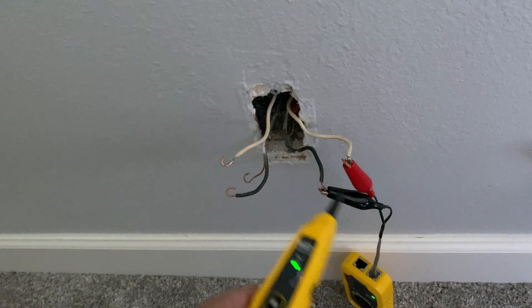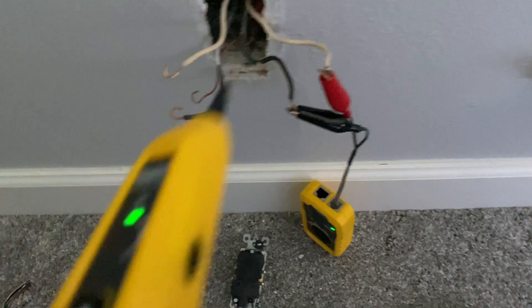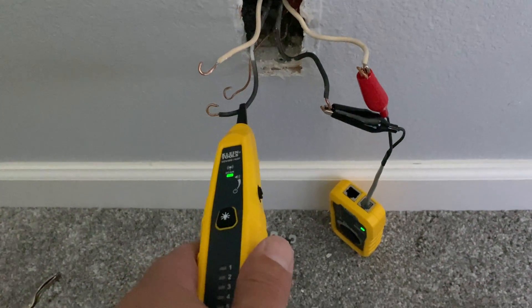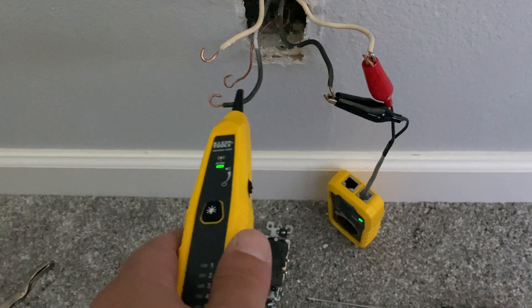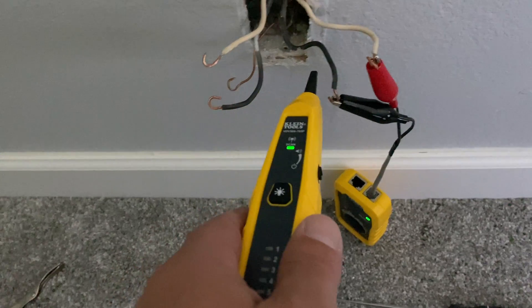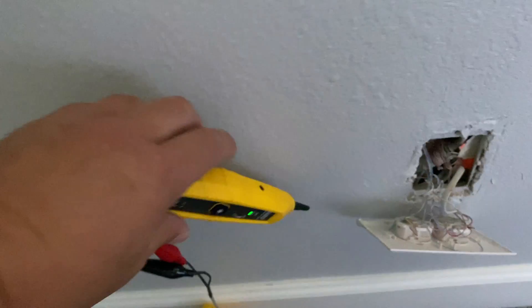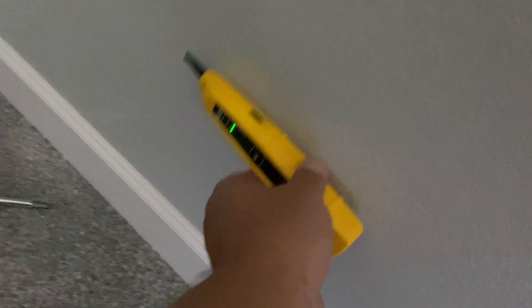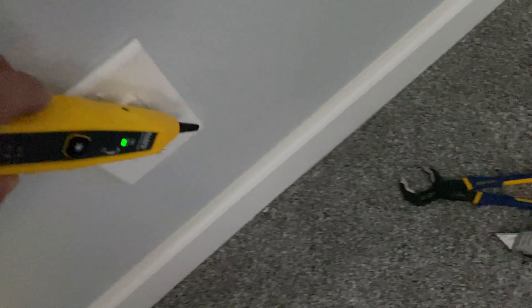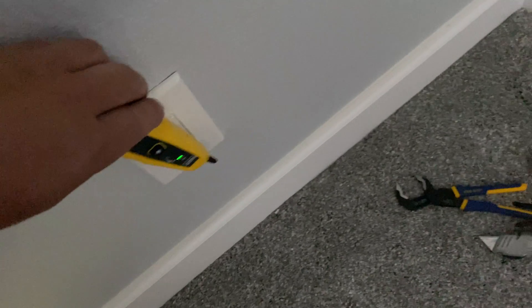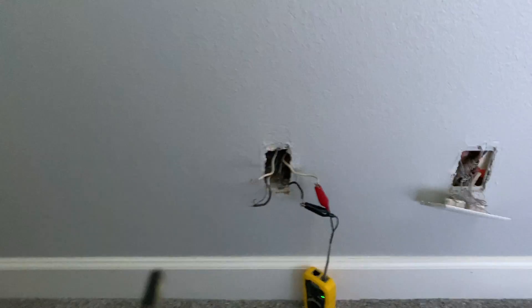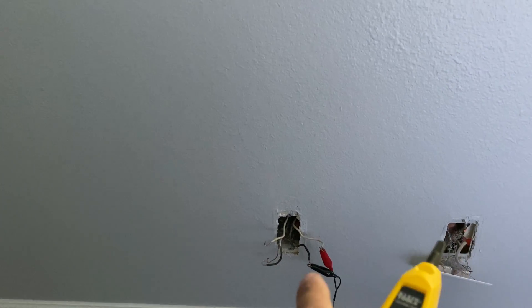So it's hooked up on the right-hand side. You can hear the tone here. I don't know if you can hear how much louder it is on that one, but now as I go over here it's pretty quiet. I go over here it's pretty quiet, but I get close to this outlet and it gets loud. So now I know that right-hand side is the power in.